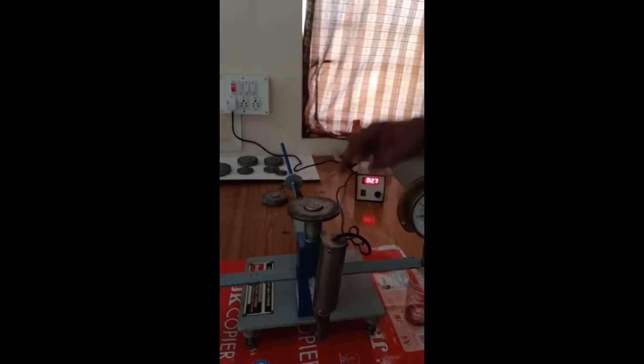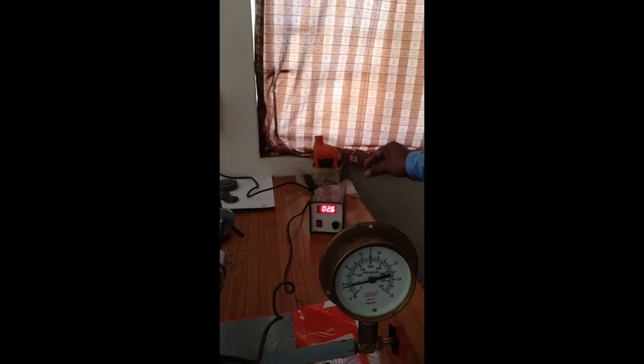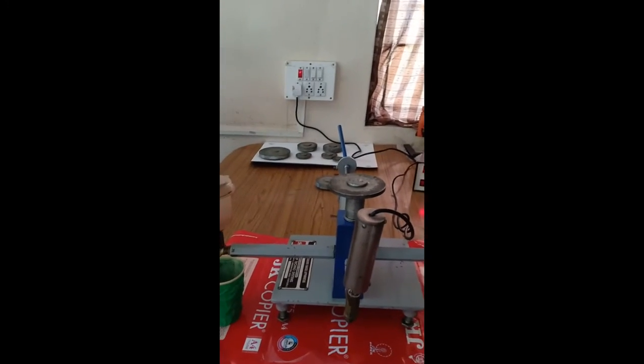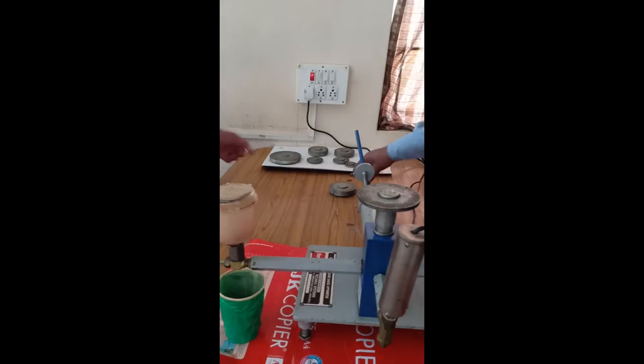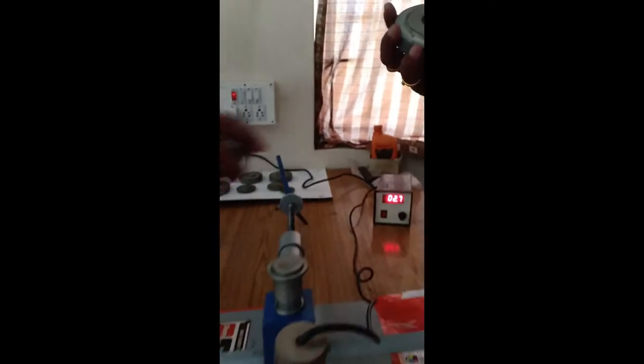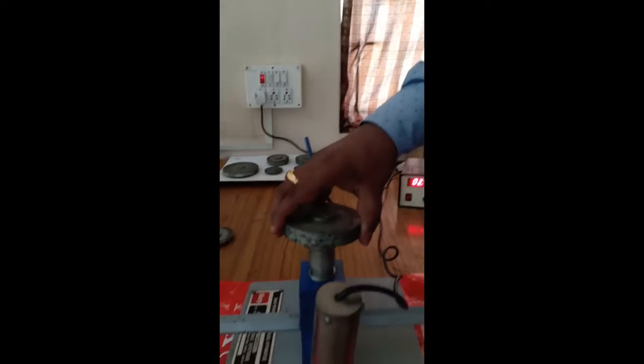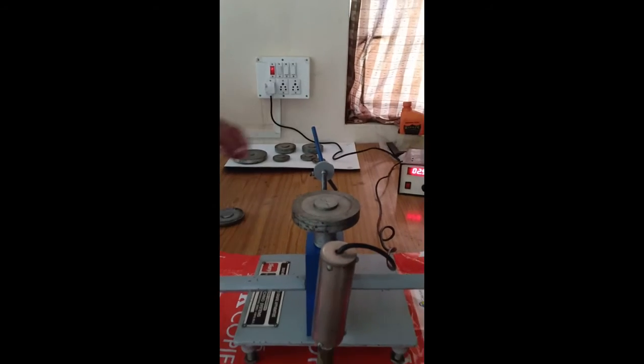This is the standard weight. I am going to calibrate this pressure gauge by using this dial indicator. Now what value am I going to get? So we are going to note down all these values, and I am going to compare the percentage of error. Now similarly again I am going to apply a 4 kg load. Again the same process. We are going to apply the 4 kg load.